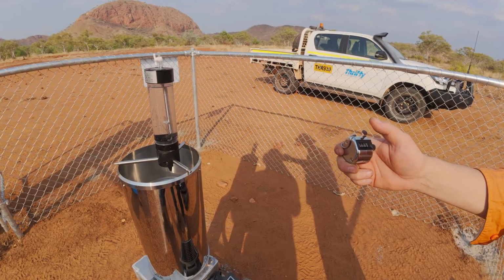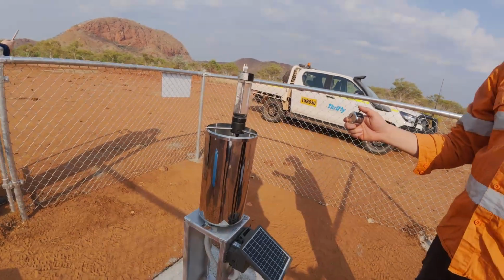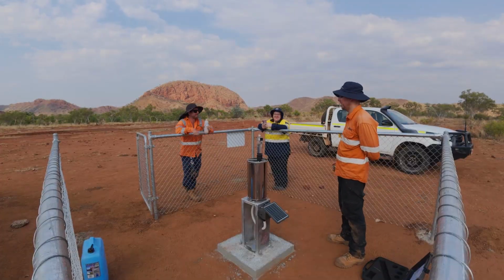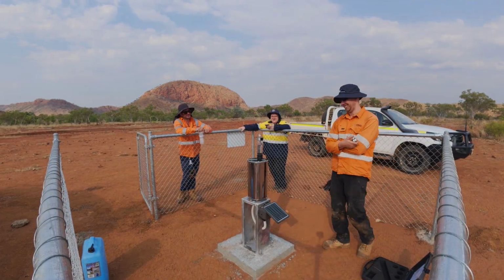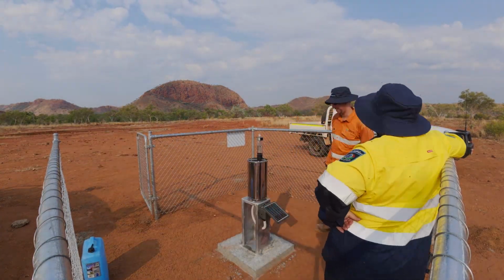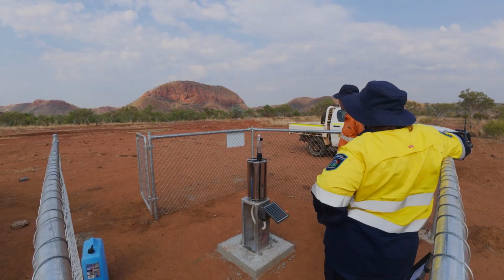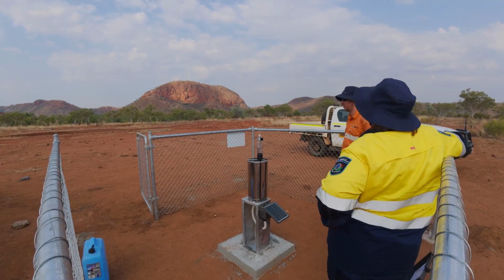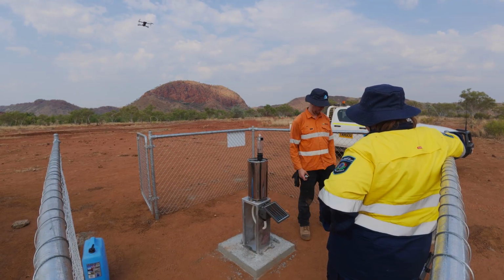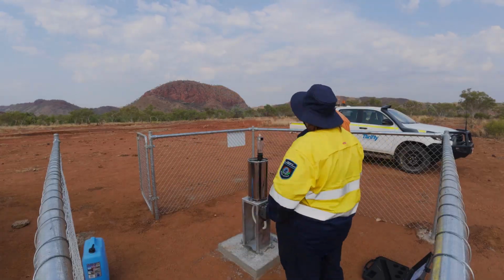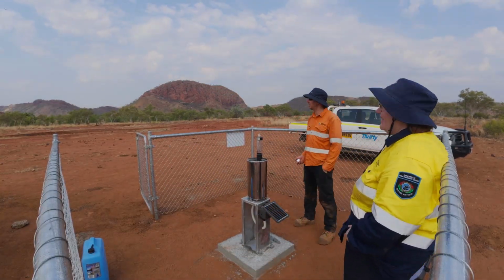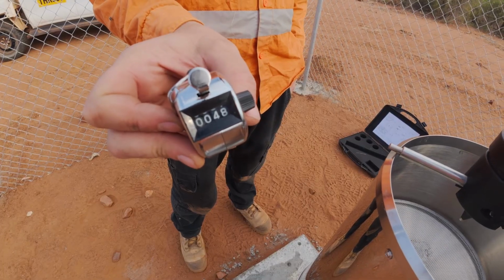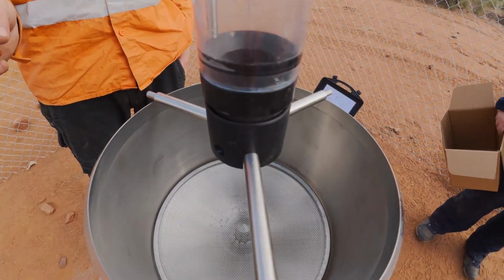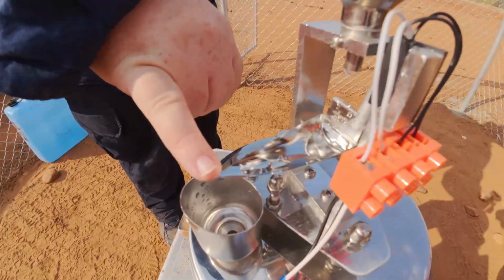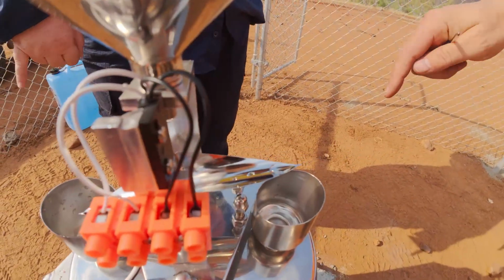Once the funnel is empty, the recorded amount of tips is checked against the calibration documentation included in the calibration kit and your rain gauge size. This calibration kit and rain gauge is expected to tip 50 times and have an allowance of plus or minus 2.5 tips to be considered accurate. The cowling should also be removed to check the amount of leftover water on the tipping mechanism. In this case, there was approximately half a tip left inside the gauge, giving us a total of 48.5 to 49 tips, well within specification.